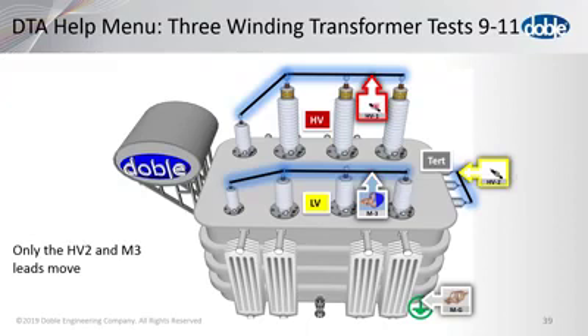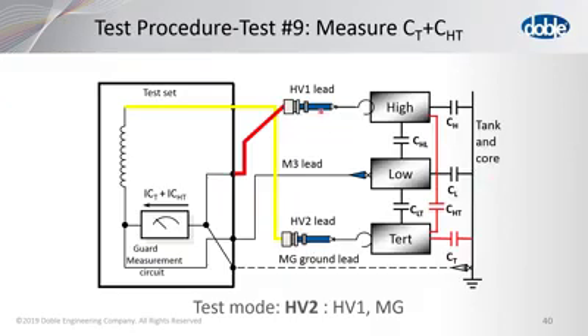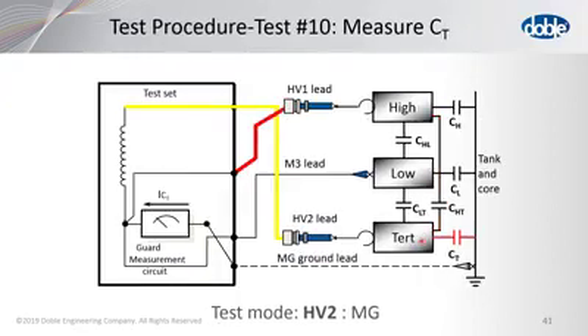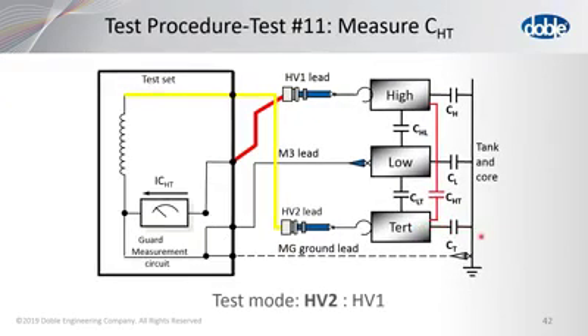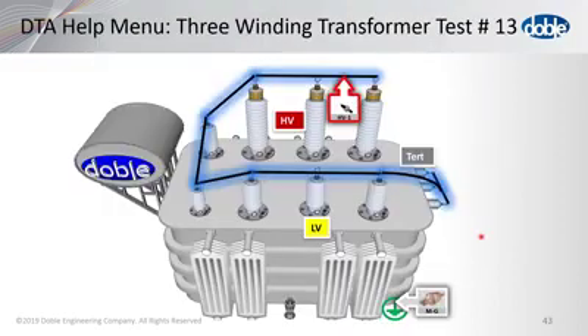The HV1 stays right where it is. Only the HV2 and the M3 leads change. Now, notice that these 2 have switched. So now we energize the HV2, and we get these 2 insulation systems. This one, of course, is being measured, and this, of course, the ground is being measured. So we get the lumped system of CT plus CHT. Then we do the CT, and then the test set automatically goes to the CHT.